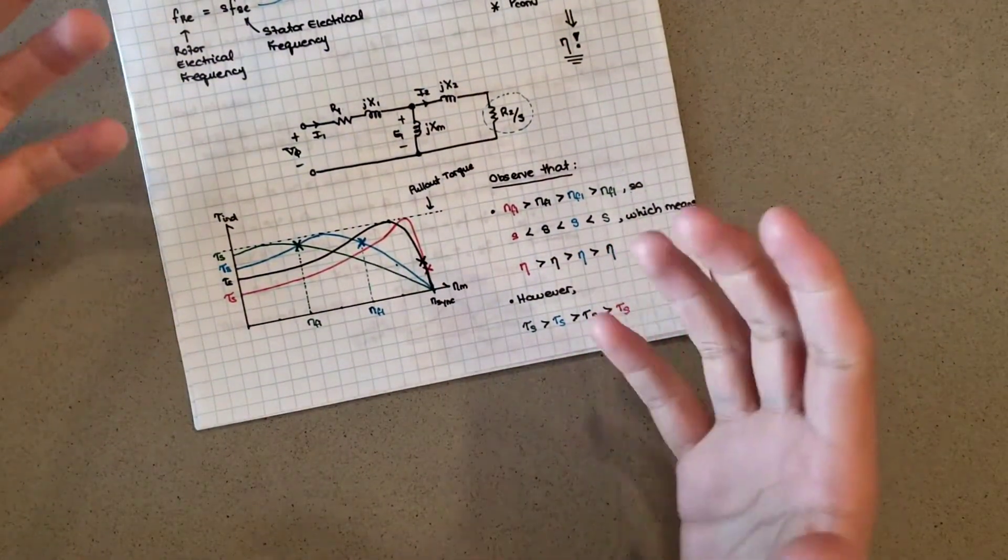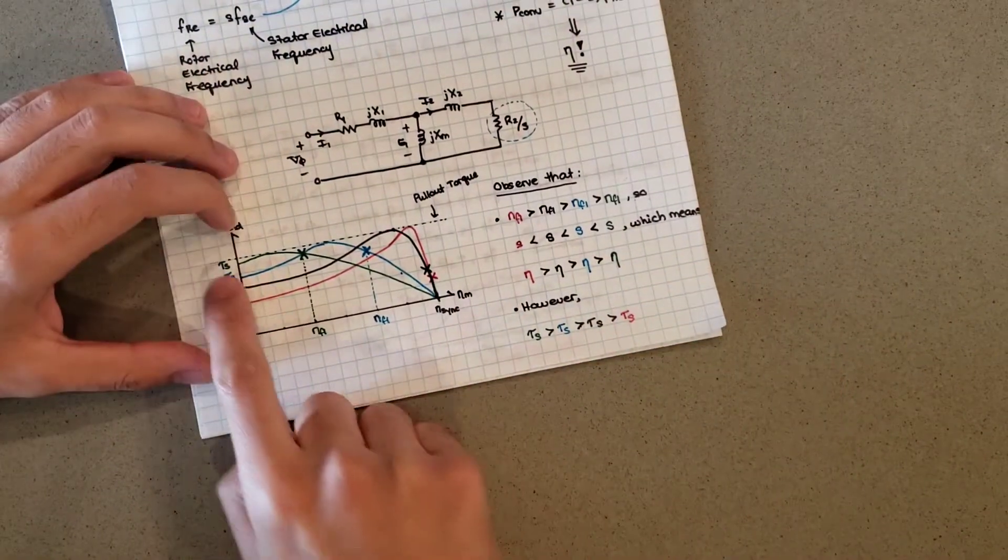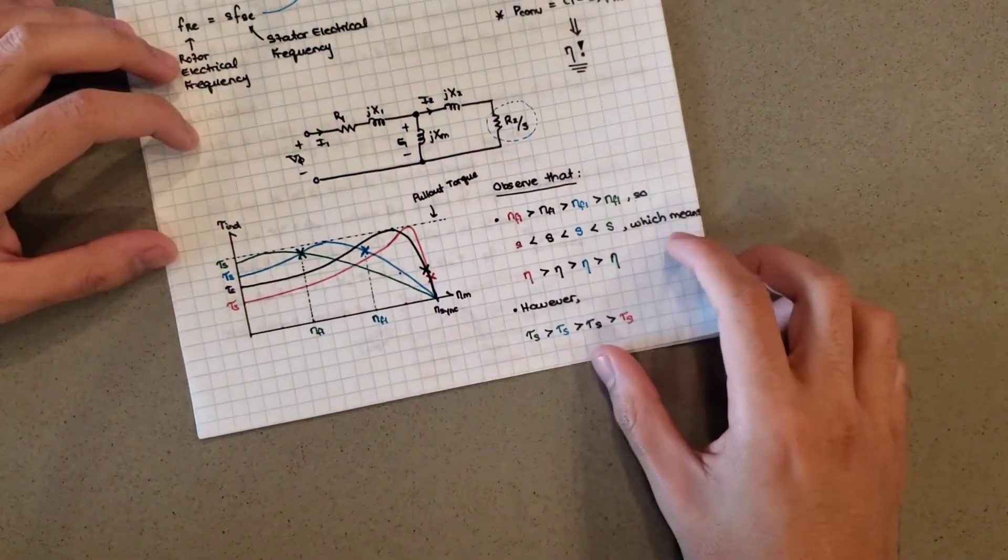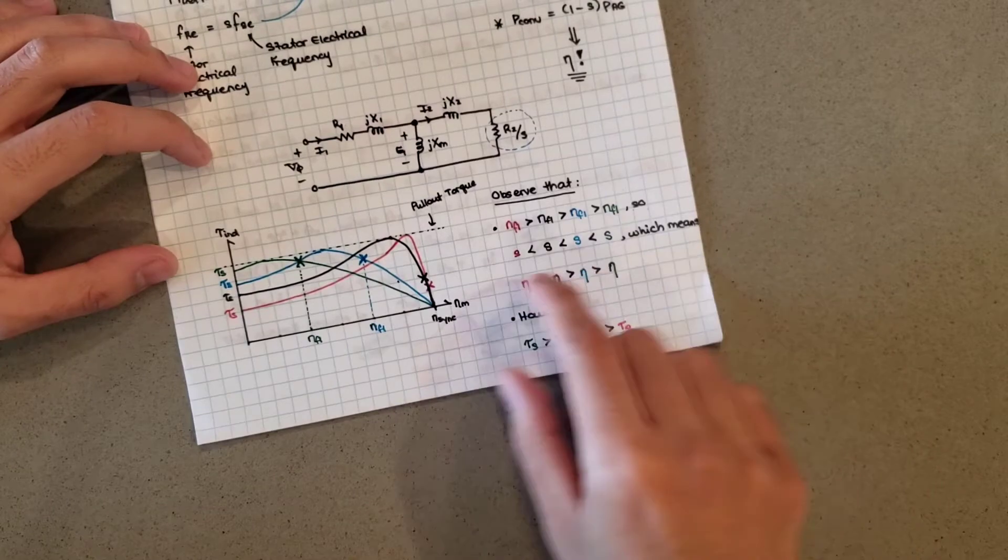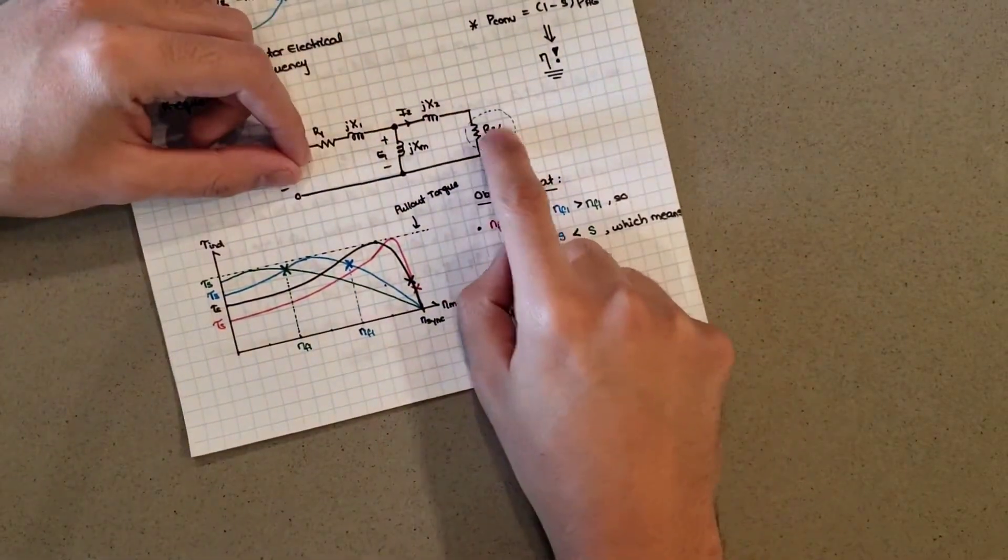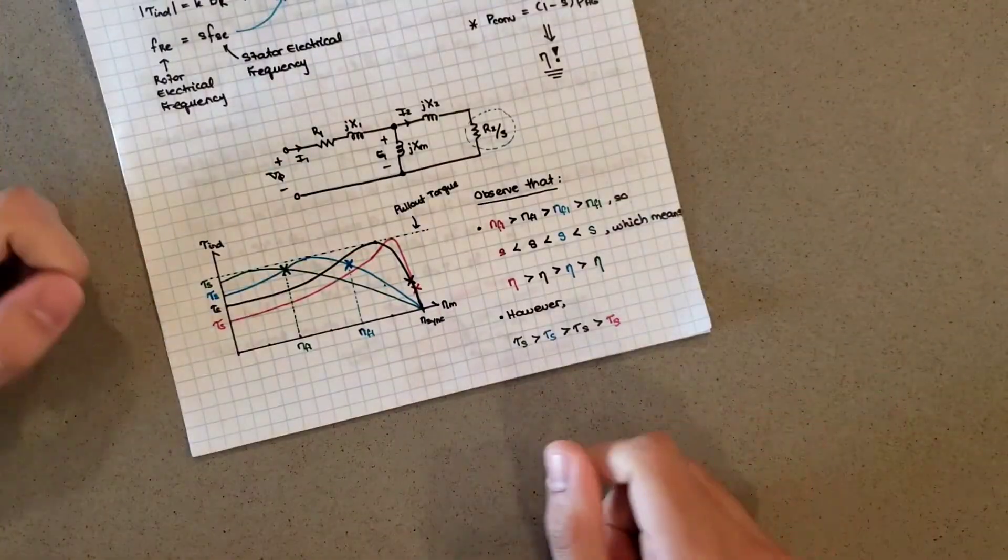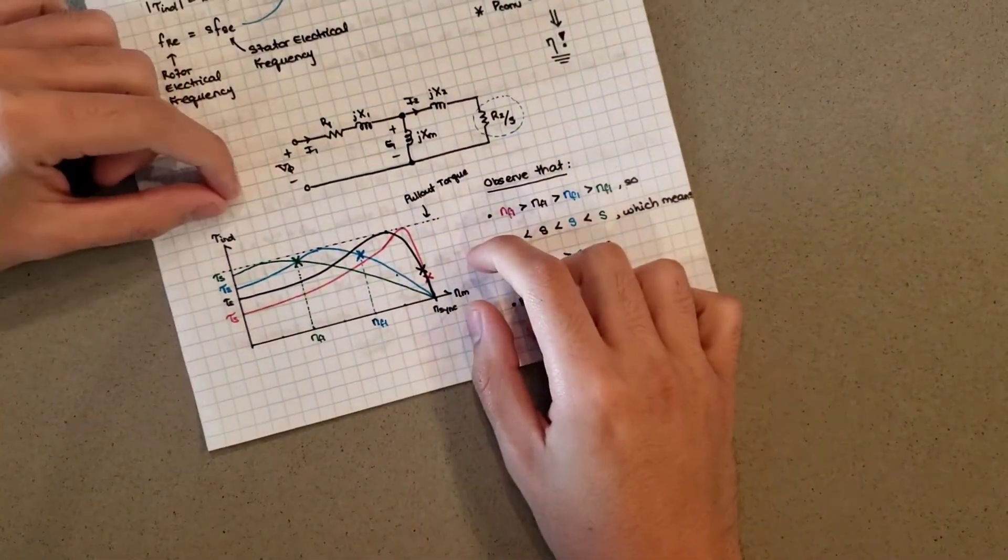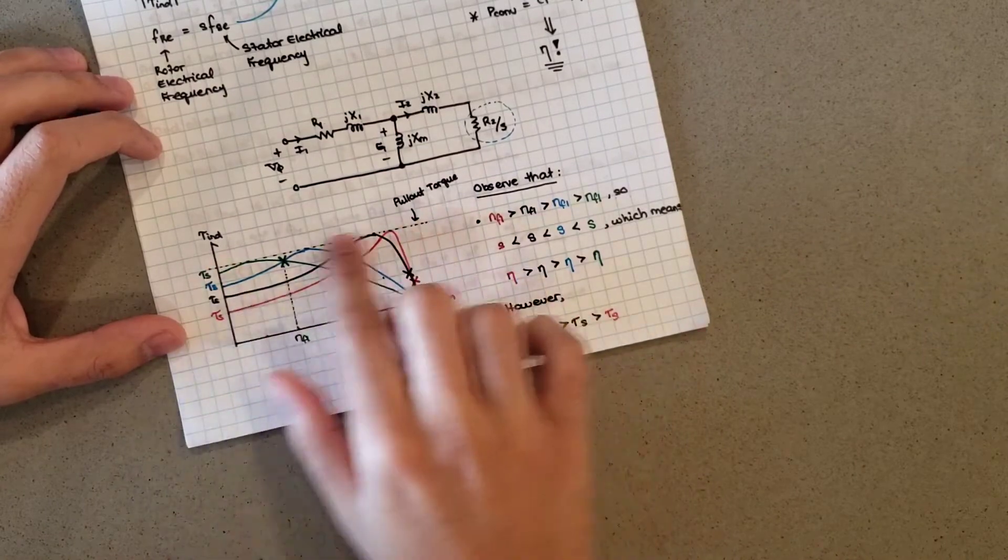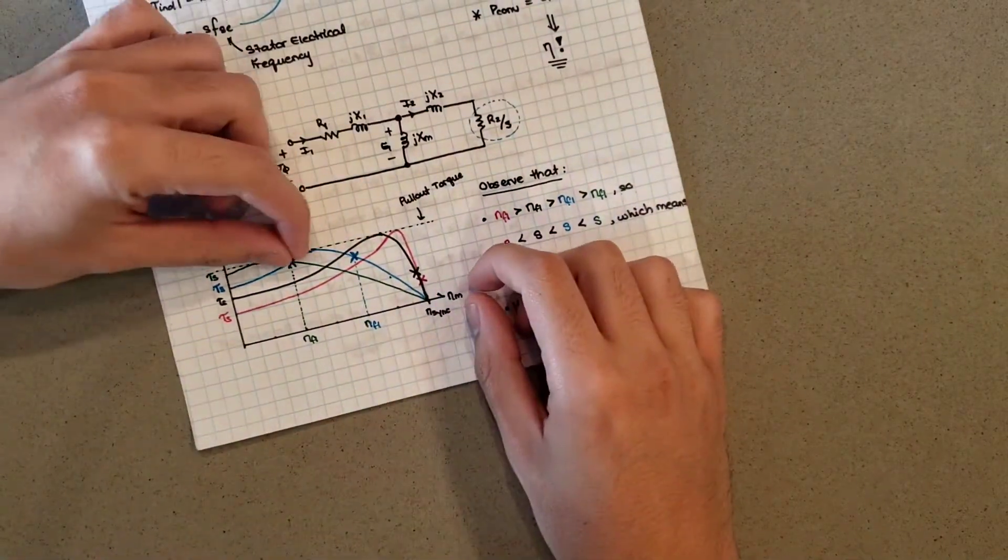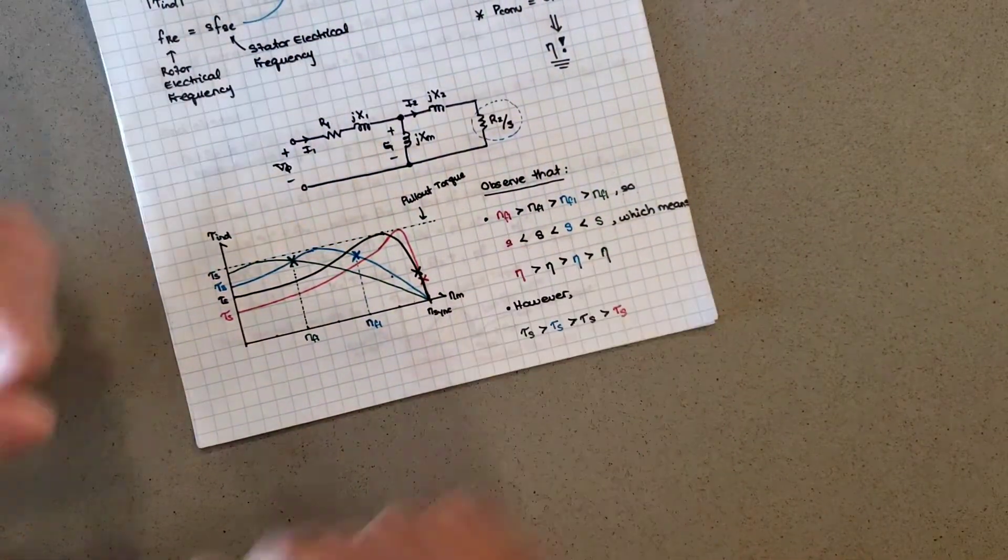However, what if I wanted my motor to have a high starting torque because of whatever load it has? Then I could go ahead and change the resistance of its rotor, either by putting resistors directly in there or by some other means. I will keep the pullout torque the same - its maximum torque capabilities are the same - but I can shift its torque-speed curve to the left a little where that peak occurs.